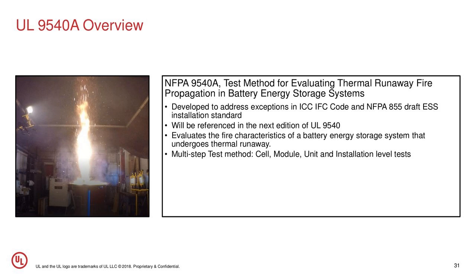It's a multi-step method. You do cell testing, which we may try to pull into 1973 as an option to help cover that portion. Then it goes on to the module, and both of those parts are information gathering. The final testing is the unit, and if necessary, the installation. The unit test repeats the module test in a complete unit, surrounded by target units and installed as intended in the final installation. If there are problems with fire getting out, etc., then the installation step repeats the unit-level testing with the sprinkler or fire suppression system operating at that time. So it's multi-step testing, and it's quite extensive.